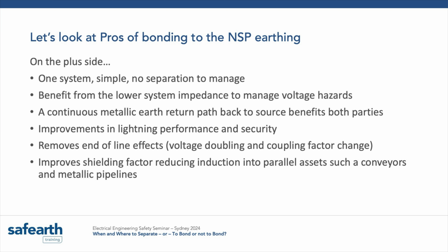All connected together, it's one system. We don't need to manage the separation, and we don't have these nasty voltage rises that can occur. The system impedances are lower, and we can utilise current return into the earth wire to keep our voltages lower. It might give us more options in the separations we want to make on our mine site, a few more tricks up our sleeve. It improves lightning performance and security at that point, as well as insulation coordination, and it improves the shielding factor too.